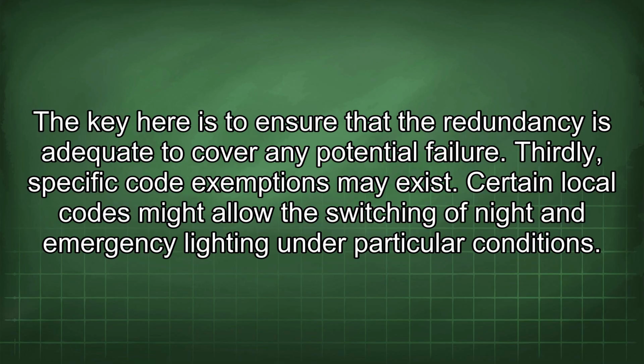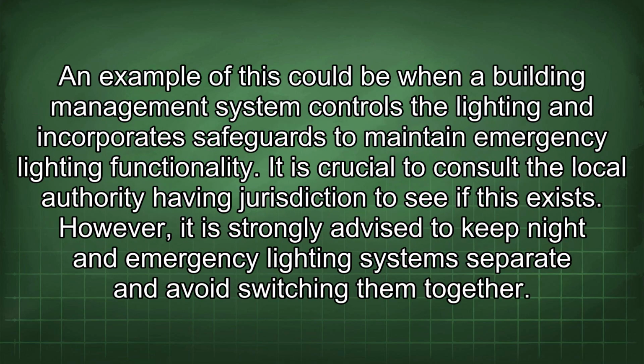Thirdly, specific code exemptions may exist. Certain local codes might allow the switching of night and emergency lighting under particular conditions. An example of this could be when a building management system controls the lighting and incorporates safeguards to maintain emergency lighting functionality. It is crucial to consult the local authority having jurisdiction to see if this exists. However, it is strongly advised to keep night and emergency lighting systems separate and avoid switching them together.